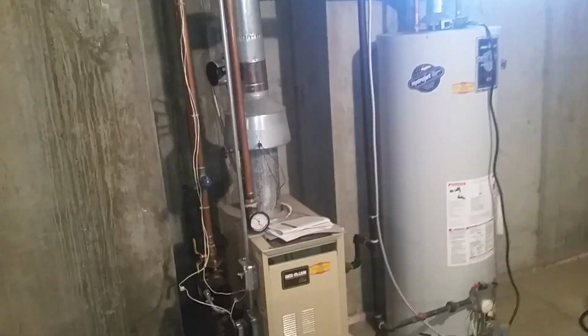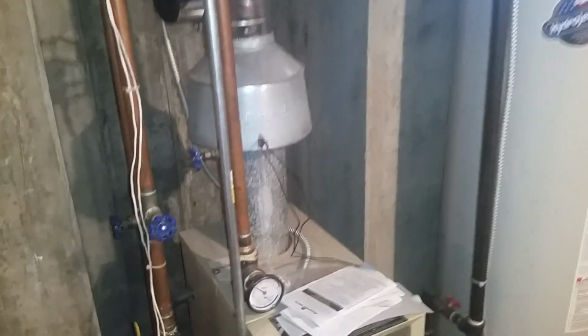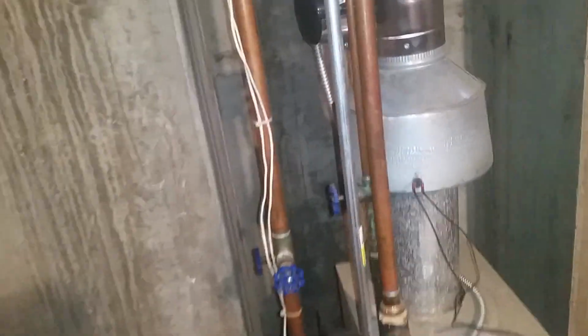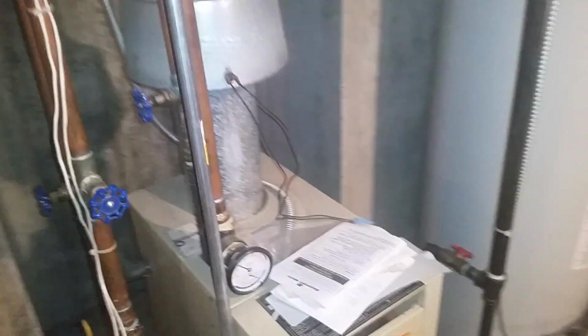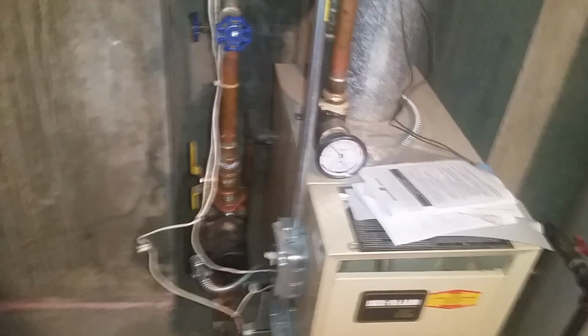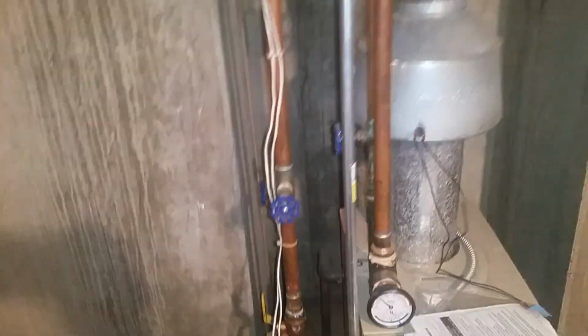So I hope that helps any of you who have no heat in one zone of your house, or you may have 3 or 4 zones and there's no heat in one zone. These are the elements to take a look at: the boiler, the zone valve, the header, the circulator, and the relay switch. Those are the important components. And of course, the thermostat, because you might have a bad thermostat that's no longer calling for heat.